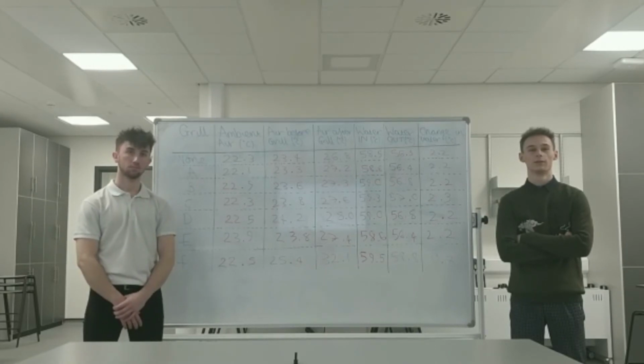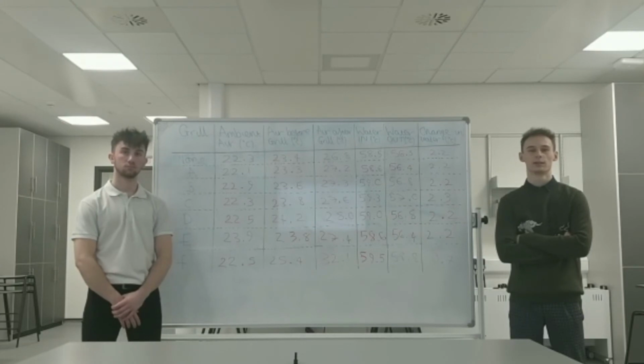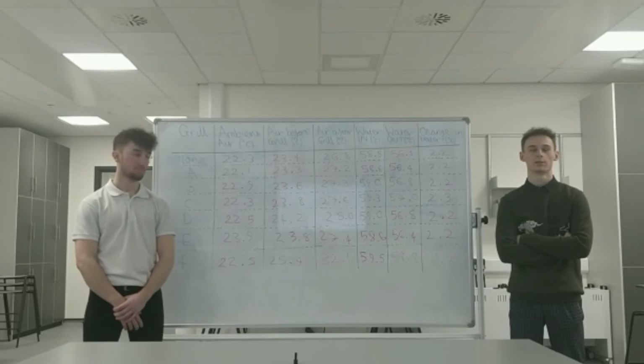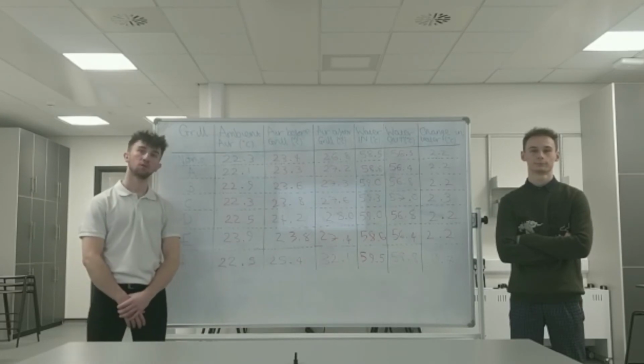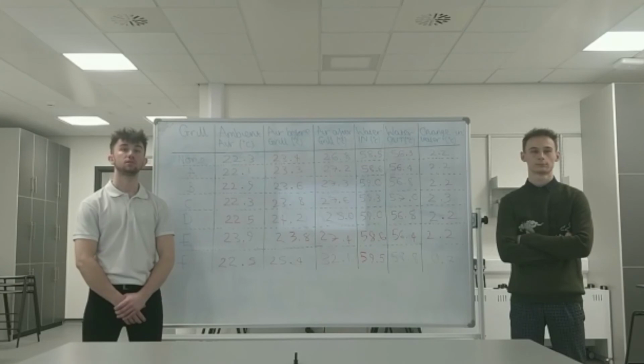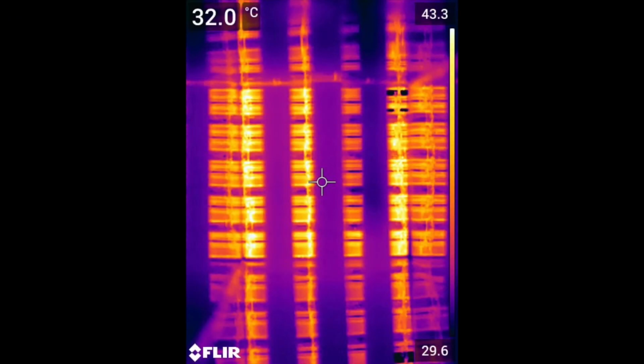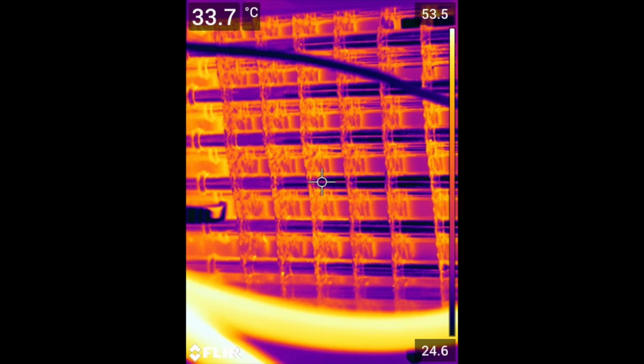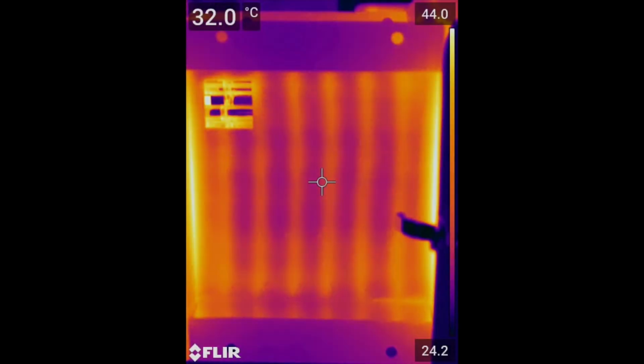However, Grill F yielded a varying temperature change of 0.7 instead of 2.2 due to its design restricting the volume of air passing through the heat exchanger. When we looked over Grill F using the thermal imaging camera, the unobstructed corner showed the highest heat transfer, whereas the obstructed area showed a considerably lower temperature.